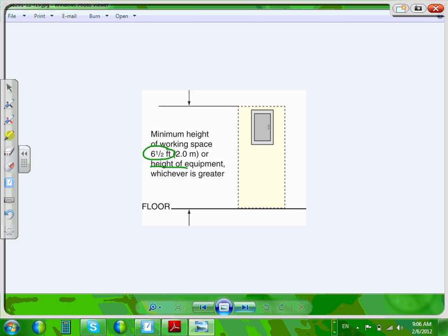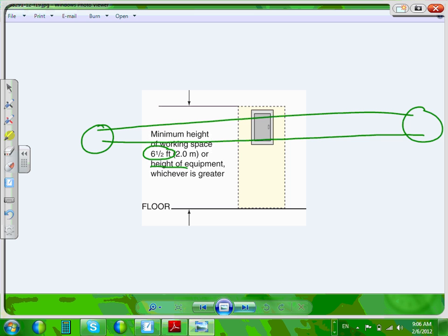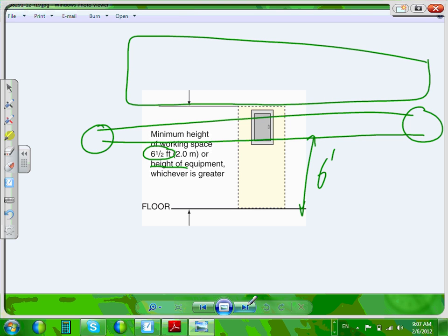What that means, guys, is you can't bring a pipe coming right in here into the working space, or a duct right into the working space. You can't do that. Let's say you put your duct right here at 6 feet. That's inside the working space. Just a mechanical duct, this has nothing to do with electrical. Now, what do I do to mitigate this? I need to put all of my mechanical equipment above this space, above that working space, which is 6.5 feet or the height of the equipment. So we know the width, 30 inches or the width of the equipment, and the height, 6.5 feet or the height of the equipment.